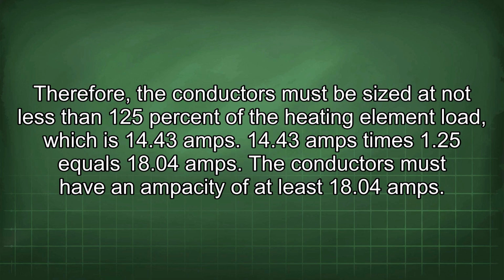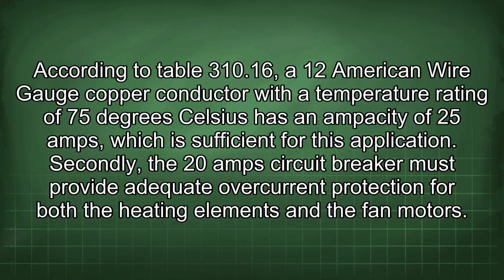14.43 amps times 1.25 equals 18.04 amps. The conductors must have an ampacity of at least 18.04 amps. According to Table 310.16, a 12 American wire gauge copper conductor with a temperature rating of 75 degrees Celsius has an ampacity of 25 amps, which is sufficient for this application. Secondly, the 20 amp circuit breaker must provide adequate overcurrent protection for both the heating elements and the fan motors.